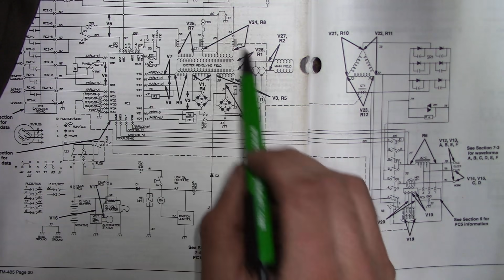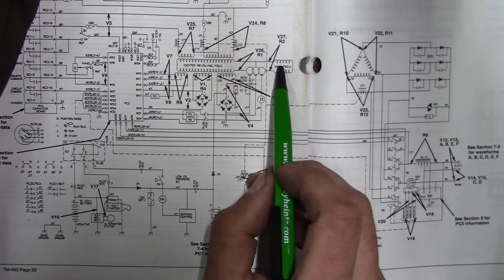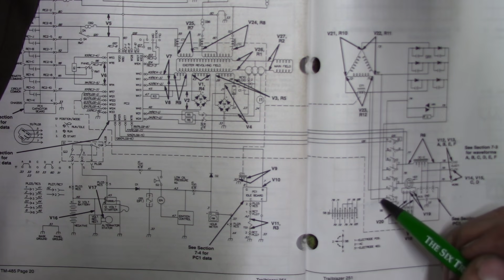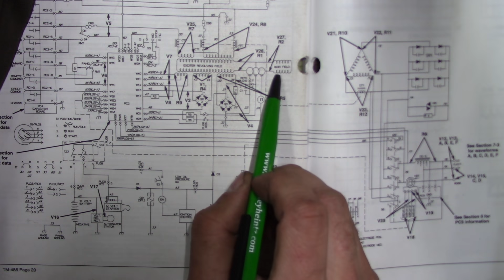I think we're going to find our problem somewhere in this region. This is a rotating field alternator or generator. Normally, like in a starter motor, the field is fixed and the rotor or armature rotates inside. This is kind of backwards - the two-pole field actually rotates inside of the three-pole winding. So this is a three-phase AC alternator, and here's the rectifier to convert the three-phase output into DC power. The exciter field winding provides power to the main field winding. There are no permanent magnets inside this alternator, so you have to have DC power in order to create the magnetism that allows it to generate electricity.